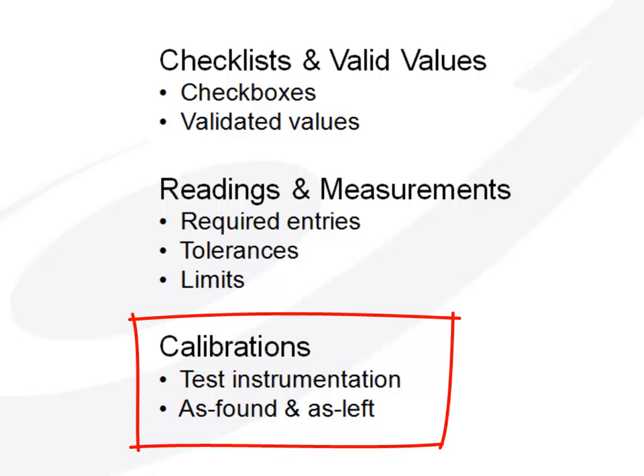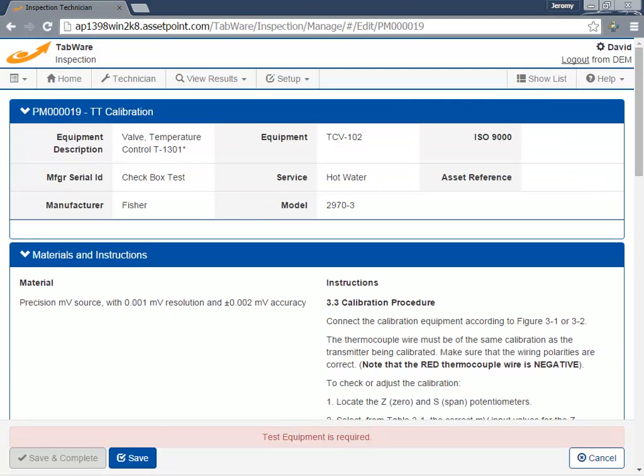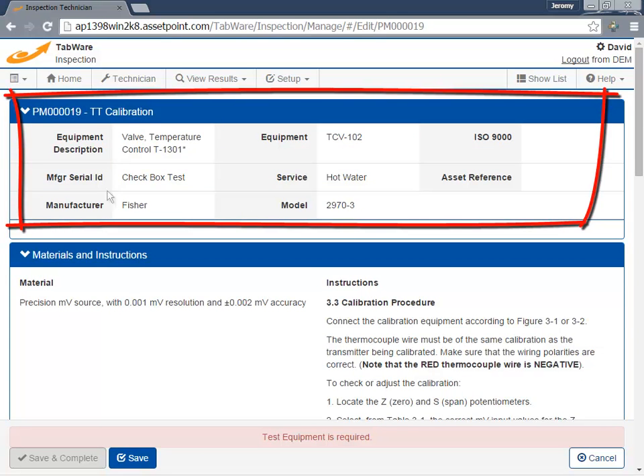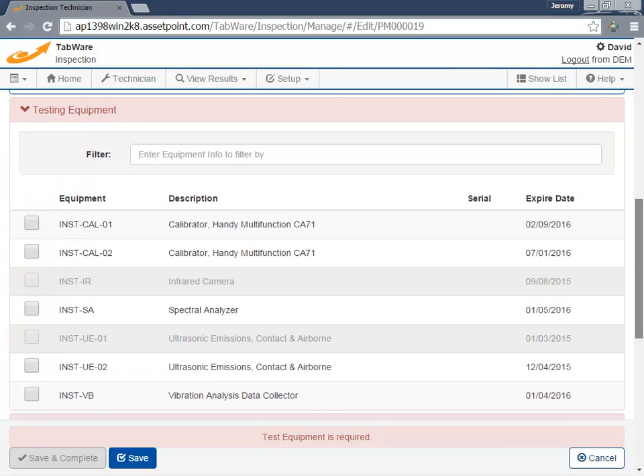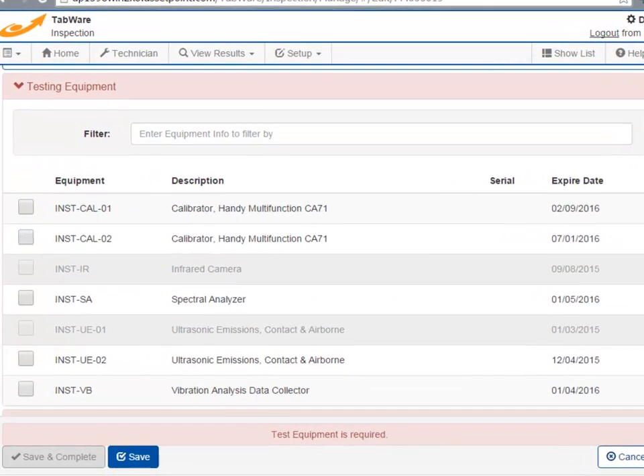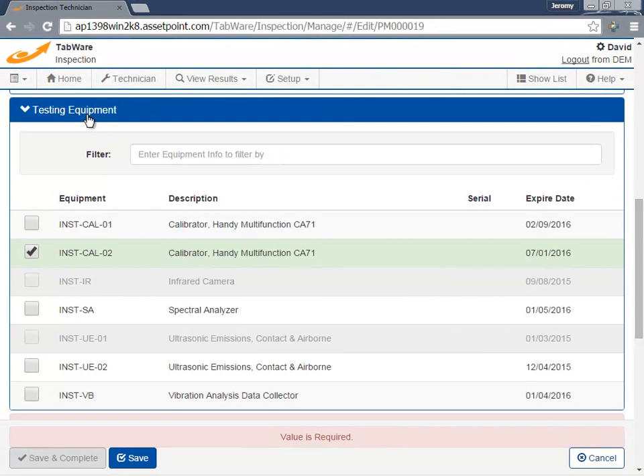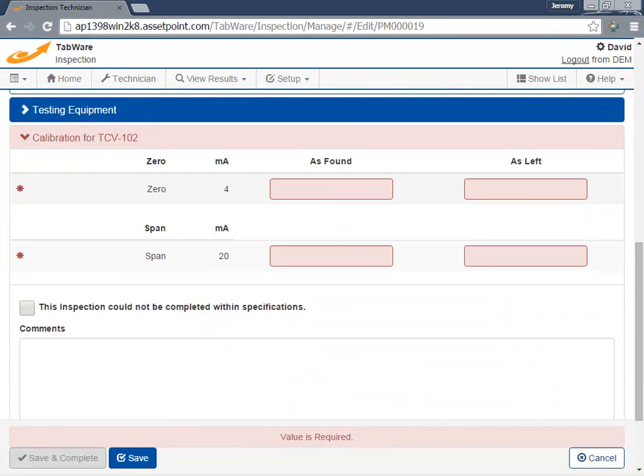Understanding that calibrations require test instrumentation and standards, Tabware Technician features added functionality specifically for calibrations. As before, we begin by reviewing equipment details and any required materials and instructions. However, for calibrations, we are required to select the test instrument used in performing the calibration. Expired test instruments cannot be selected. Once we select a valid instrument and standards as applicable, we can continue to perform the calibration.